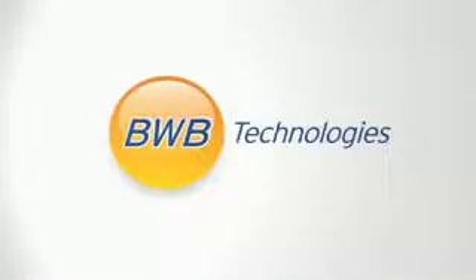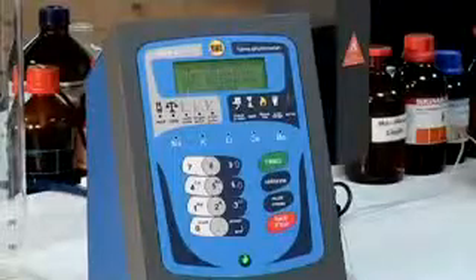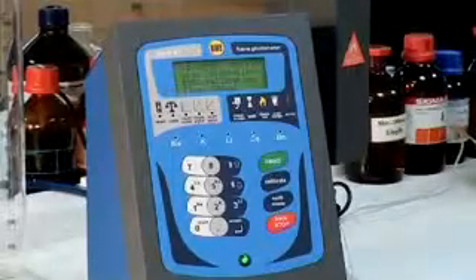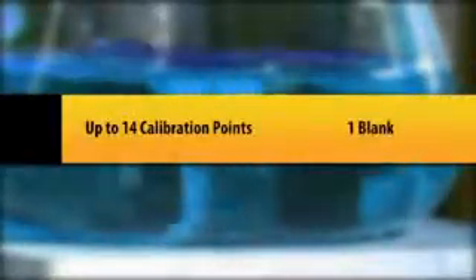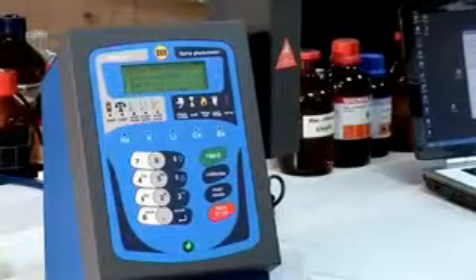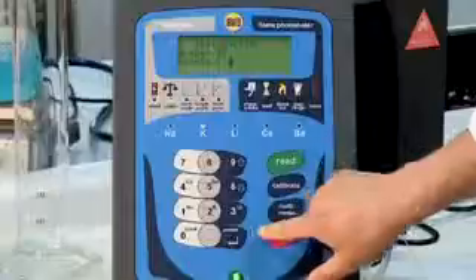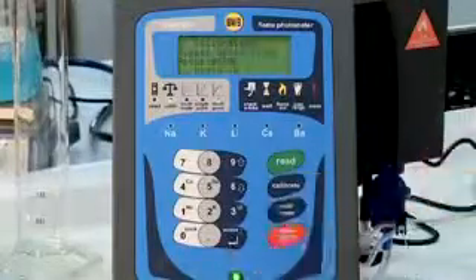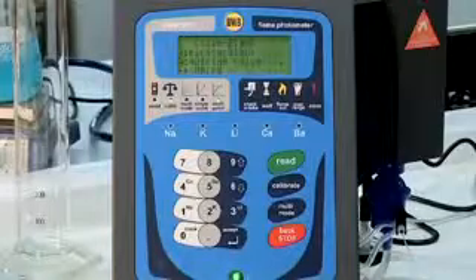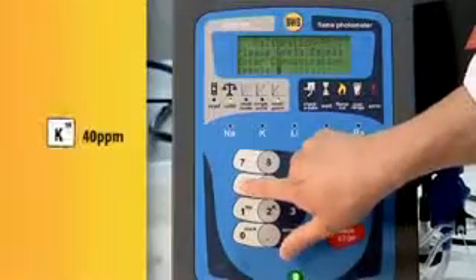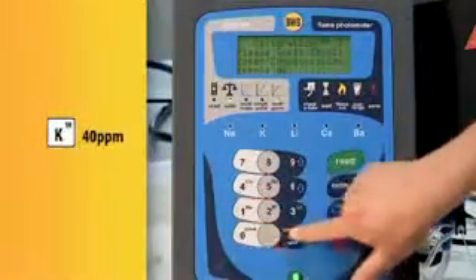The Bwb Xp will offer prompts as we go through the steps of a calibration. From the main menu, choose Calibrations. Go to Calibrate Ions and choose Potassium. For a single point calibration, enter 1. Begin by aspirating the blank and press the blank key to begin the process. Of course, as the Bwb Xp is warming up, we recommend you aspirate the blank continuously. While we are waiting for the process to complete, we can follow its progress on the FP PC.